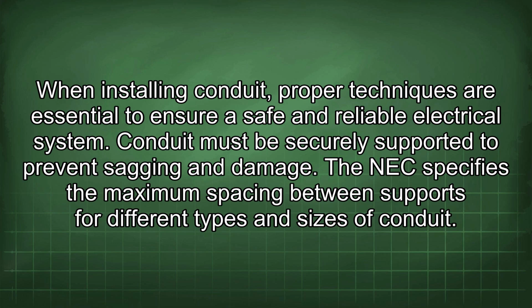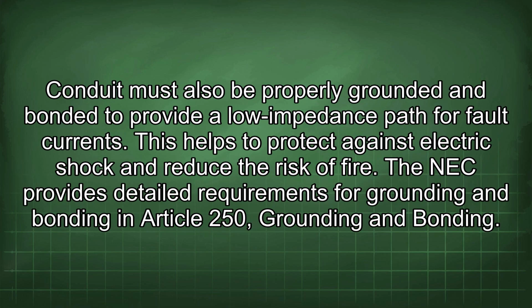Conduit must be securely supported to prevent sagging and damage. The NEC specifies the maximum spacing between supports for different types and sizes of conduit. Conduit must also be properly grounded and bonded to provide a low impedance path for fault currents. This helps to protect against electric shock and reduce the risk of fire. The NEC provides detailed requirements for grounding and bonding in Article 250, Grounding and Bonding.